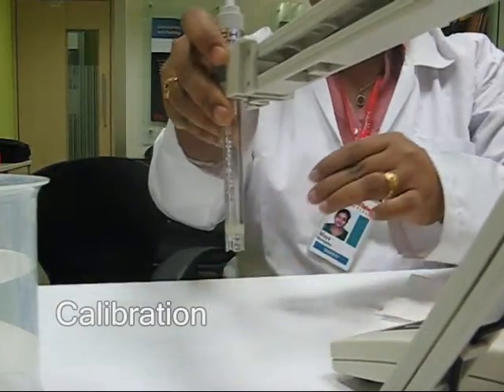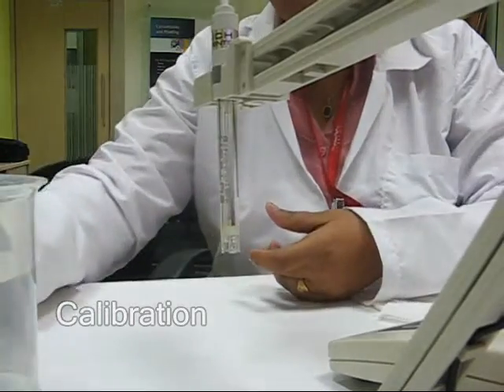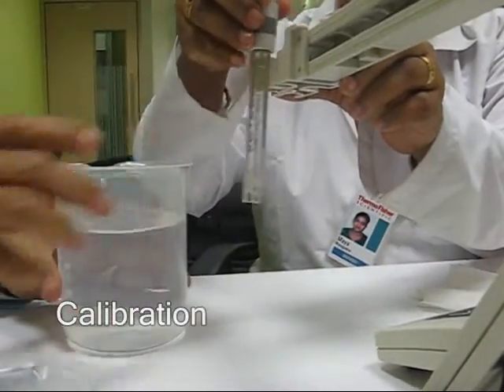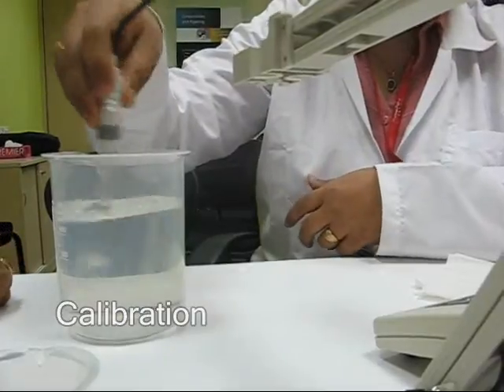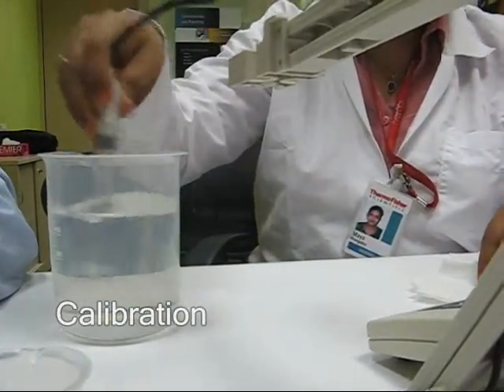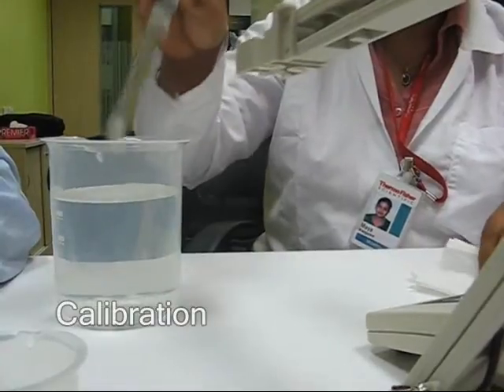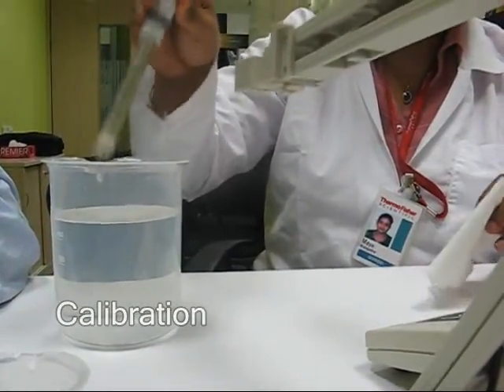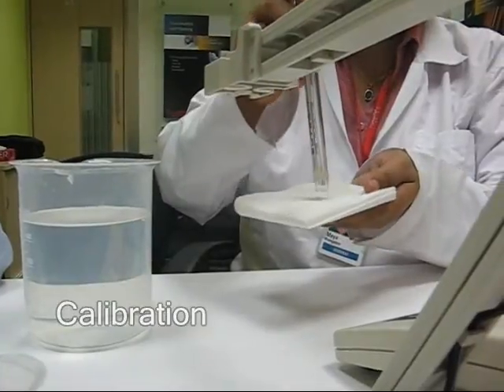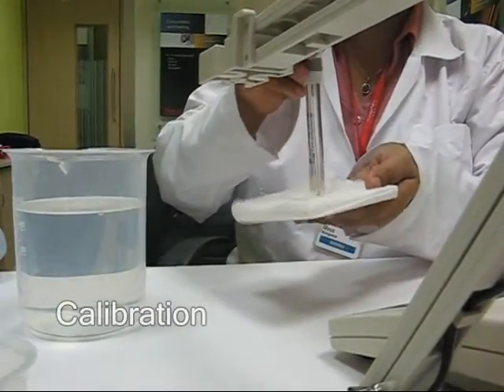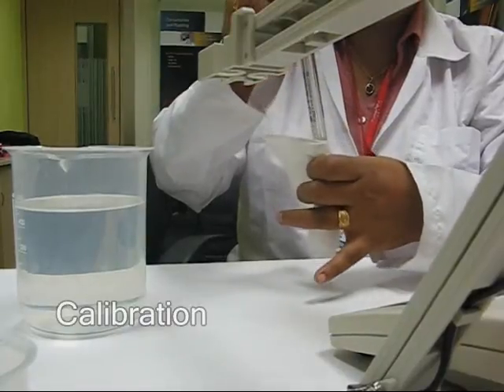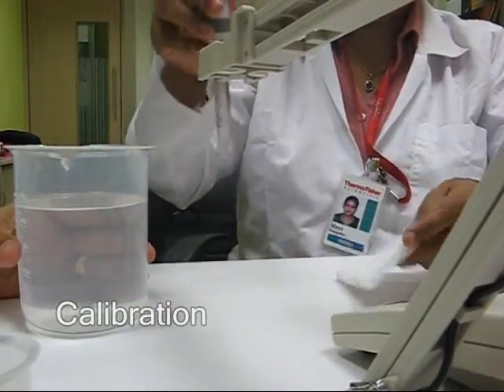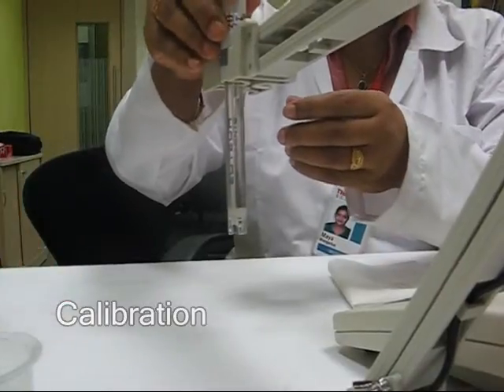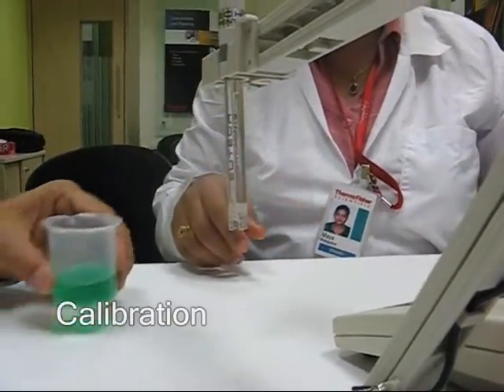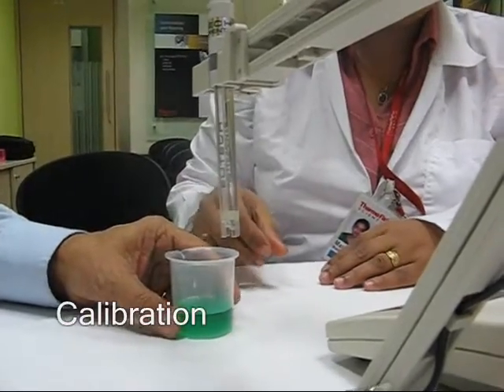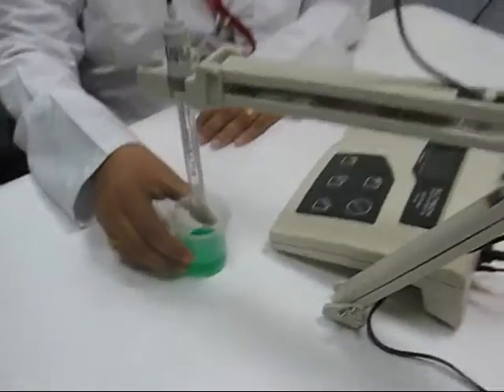Put it away. You may want to remove the electrode from the stand and then wash it in a beaker of water. Rinse it nicely and then just dab it dry. It's not a good practice to rub any paper or cloth against the electrode because that causes static buildup on the electrode. So it's always a good practice just to dab it around the electrode. That's good. Let's place the electrode back onto the stand now and take the first buffer.